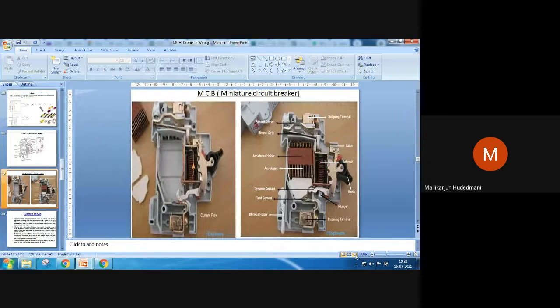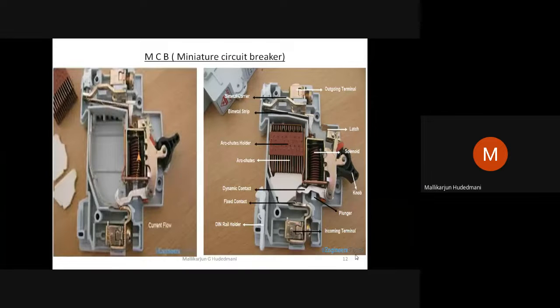You can just see this internally how it looks like. I have just shown you an open one. MCBs have a lever with a spring mechanism, a solenoid coil, and contact out, contact in. Some manufacturers have the incoming contact on the top and outgoing on the lower. Somebody will have an incoming contact at the lower and outgoing on the top. It doesn't make any difference.